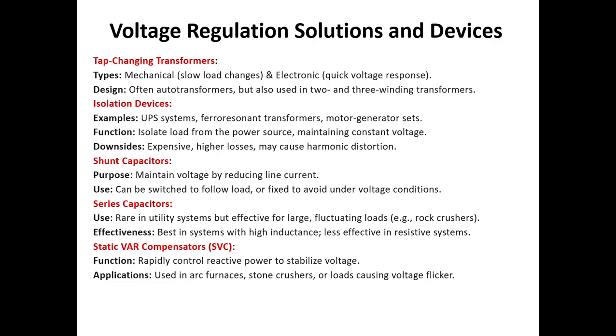Then we can use the series capacitor also. This is rarely used in utility systems but is effective for large and fluctuating loads, for example rock crushers. If you think about a rock crusher, we use series capacitors to improve voltage regulation. Now effectiveness: it is best in systems with high inductance, and less effective in resistive systems. So if high inductance is there, then we can use this series capacitor. But if there is a more resistive load, then we do not use it, because it will be less effective, meaning efficiency goes down. So these are the devices we use for voltage regulation purposes.